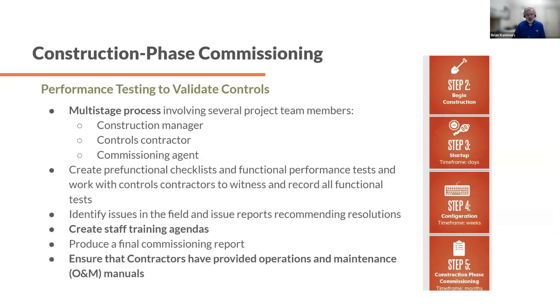Then the construction phase commissioning—this is where the building's being built, you've got equipment showing up, you've got controls going in, and you should have a checklist to make sure everything's in place, everything's delivered, everything is connected. Then you go through to make sure that sensor actually connects to the piece of equipment you think it does, not to the piece of equipment next door. These things happen all the time.